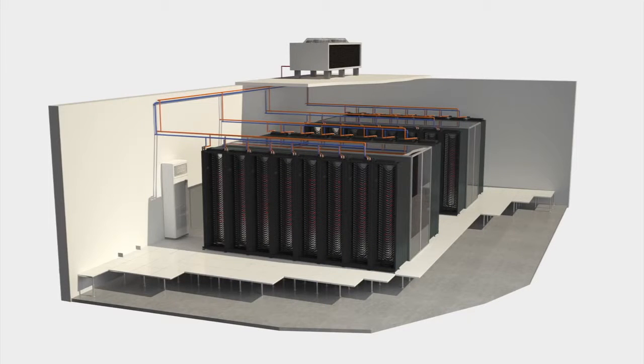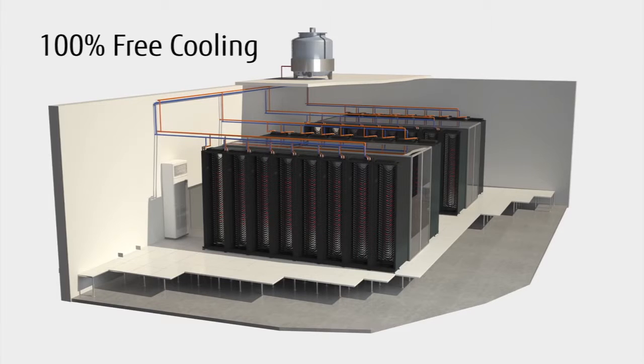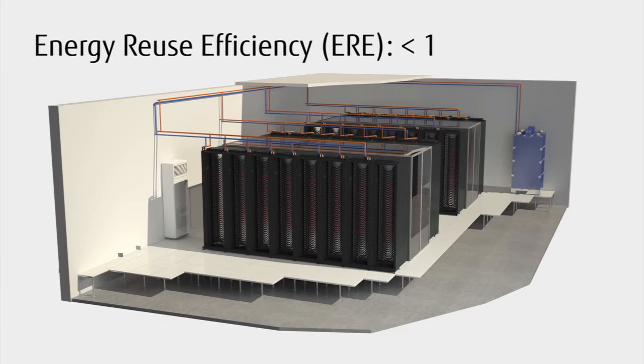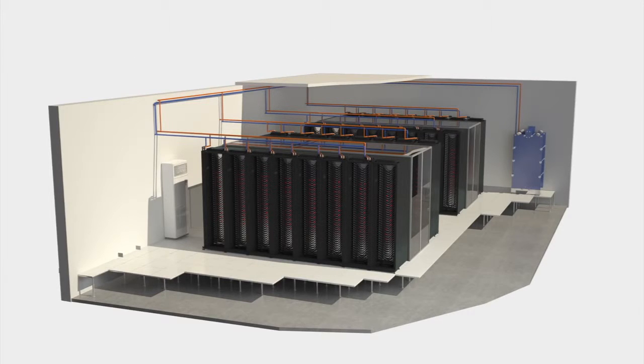Heat can be removed from facilities water with an outdoor dry cooler or a cooling tower. Both are capable of utilizing 100% free ambient outdoor air for cooling year-round in nearly every location on Earth. The high exit water temperatures provided by the CDU make waste heat recovery of server energy possible. The recycled energy is capable of providing space heating, water heating and even space cooling via heat pump systems.